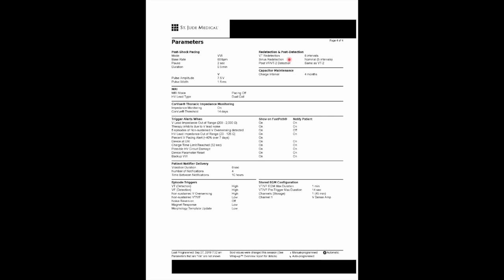All right, so looking here, page 4 of our parameters, again, this is just breaking down a little bit more of the nitty-gritty here with ICDs. These are always longer sets of parameters because there are so many different things to consider. So this is our post-shock pacing mode, our base rate. Notice how it goes from 40 during normal lower rate limit settings, but if a patient were to be shocked, it is going to temporarily start pacing them at 60 for a certain amount of time.